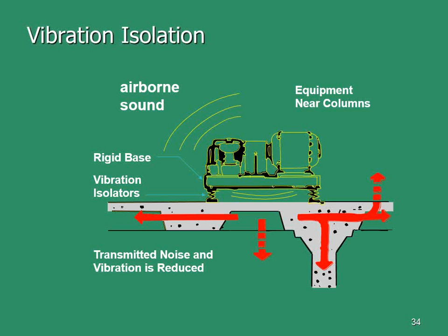What happened is we had vibration isolation under the cooling tower, and we had vibration isolation between the cooling tower and the piping. As that piping ran down the shaft, every so often it had to have seismic restraints. On the 5th floor, they reefed on the cables—they turned the turnbuckles a few too many times and turned it into a taut guitar string.